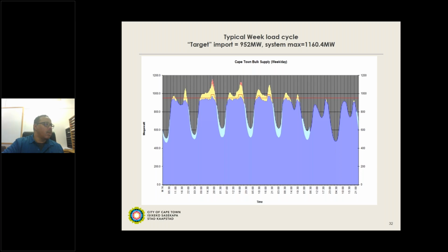The turquoise portion is the power we take off the grid in the evening at lower demand periods, which allows us to pump back up. We take about 51 to 52 megawatts per machine for pumping. The key agreement between Eskom and the City is that we must not exceed the red line, the NMD, which in this example was set at 952 megawatts, though it varies depending on circumstances. We have to ensure we stay below that line.